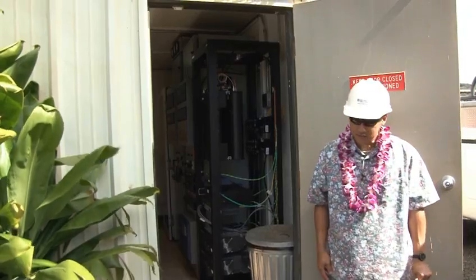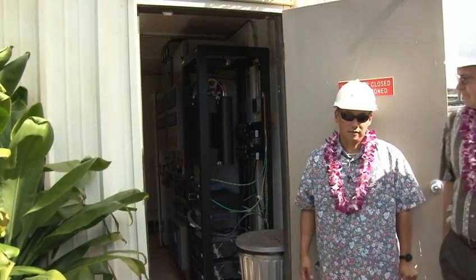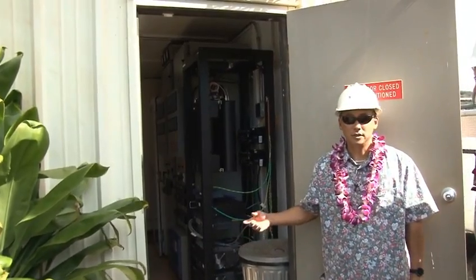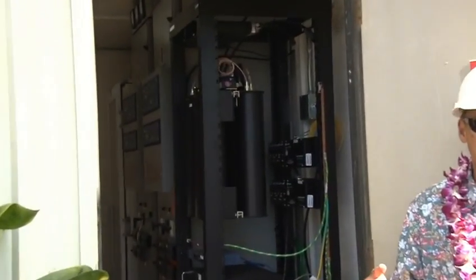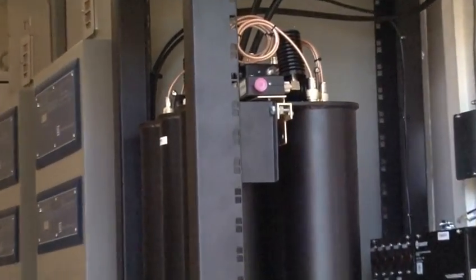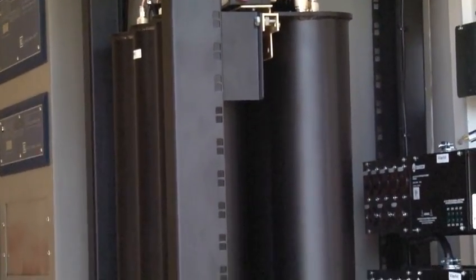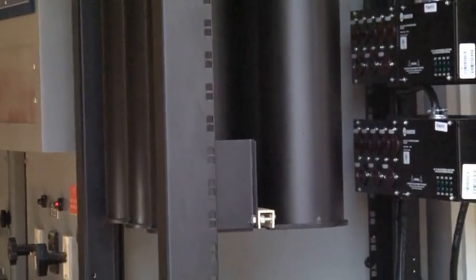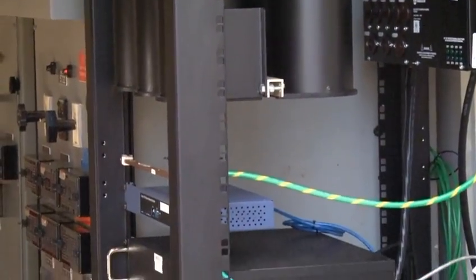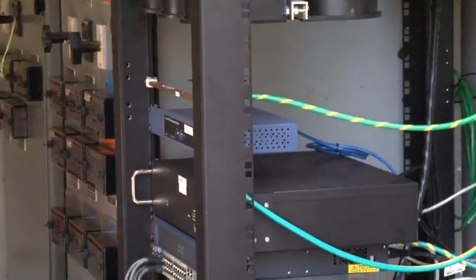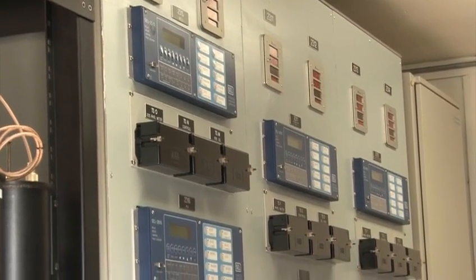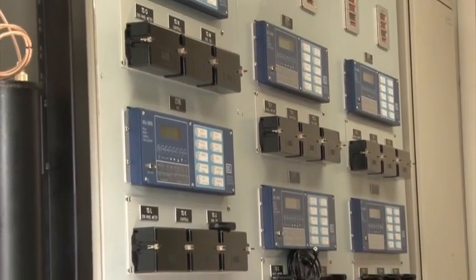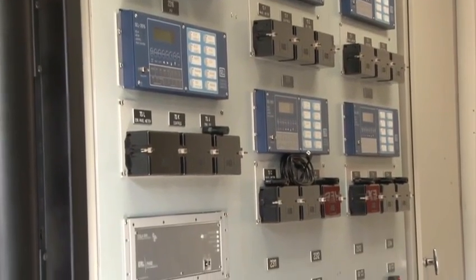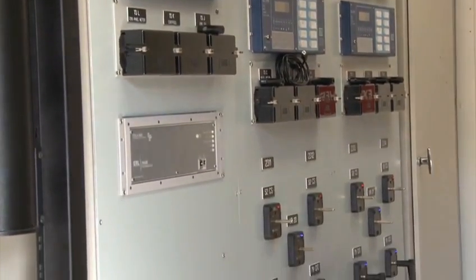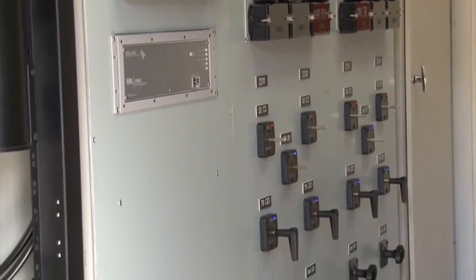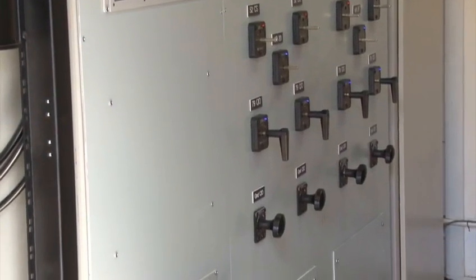So this is the control room. Basically, it's the brains of this whole station. All the communications, the sensors, the inputs, not high voltage stuff, just low digital or analog information, all gets transferred from the outside bus and from the battery, all gets wired in through here. So we talk about protection of the system, a lot of computerized electronics. We've got a radio system housed in here. We've got a high-speed recorder housed in here. If you go out and look, we have a graph showing the event. That's actually from a high-speed recorder.